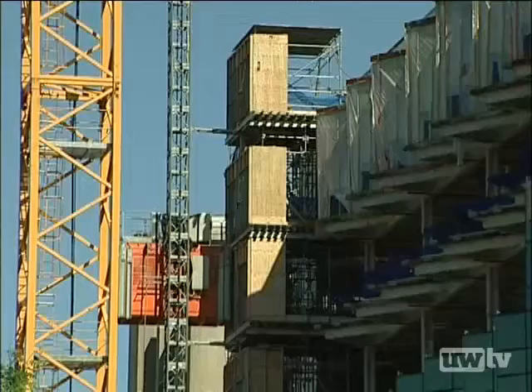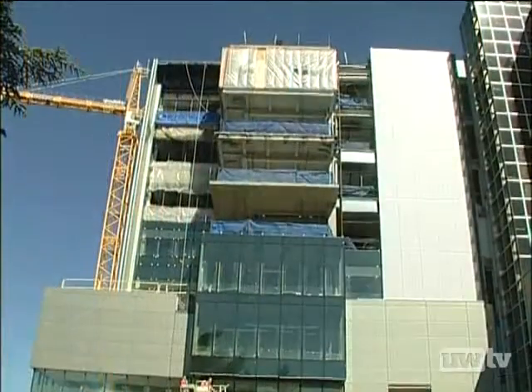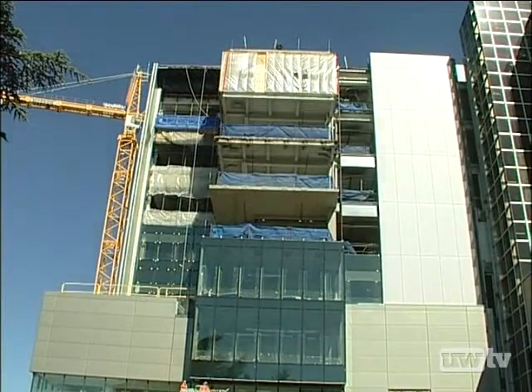And what we found out was that the largest energy use in a hospital is for heating. More than 60% of its energy is used for heating, and yet it consumes enough energy internally, and most of that energy is turned into heat, that it shouldn't need heat until it gets below 20 degrees outside. So it was sort of like, Houston, we have some sort of a problem here. The lab developed strategies to construct hospitals that are 50% more efficient at no additional cost.